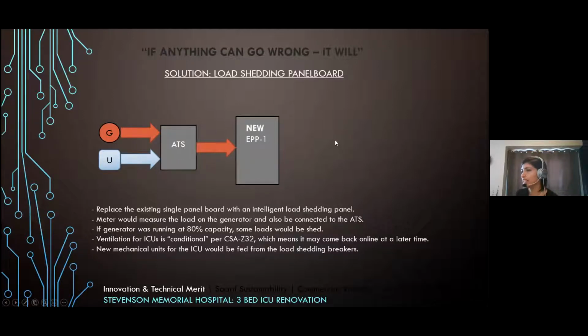Our idea was to replace that existing panel board with a new panel board, refeed all the existing loads and the vital ICU, but then also install a meter on that panel, which would be connected and measure the load on the generator, such that if the generator reached close to its capacity, certain breakers in the panel would open and shed some load, allowing us to salvage some of the load on the generator.